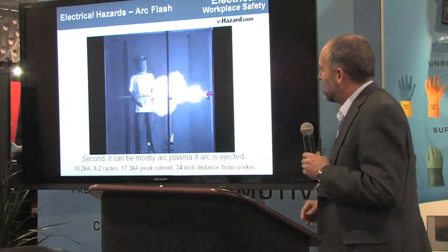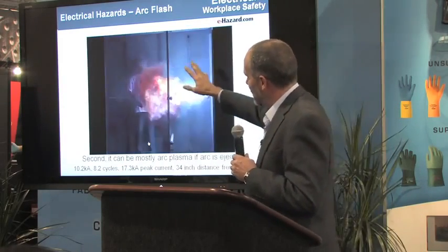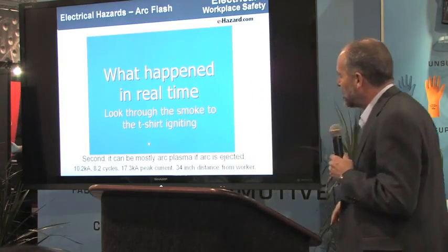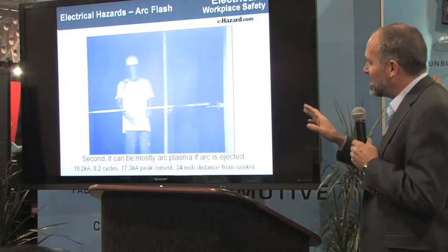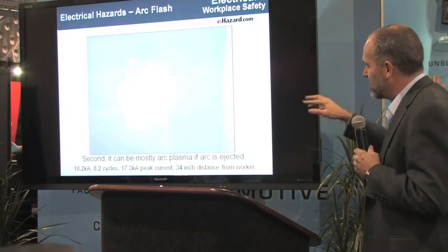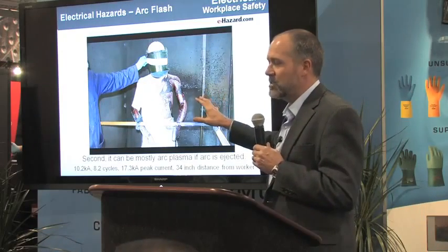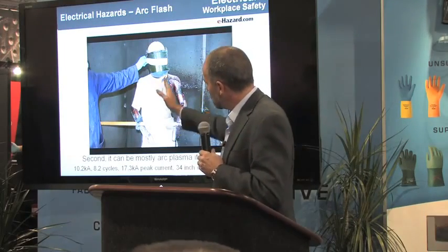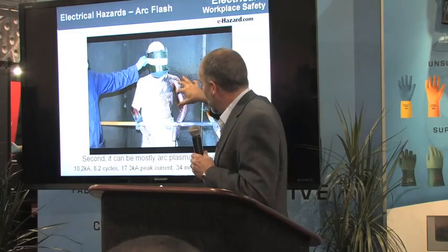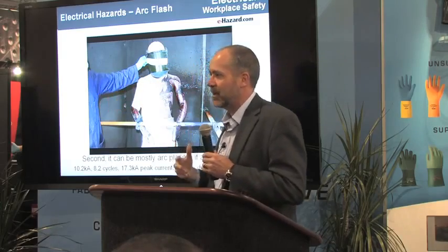Plasma is rough. It looks like just a little flowing thing coming through there. This is a sixth of a second you're watching here — here's what happened in real time. I have a cotton t-shirt on the mannequin. We hit him with that arc flash that you saw bellowing out toward him, and it was about 45 seconds it took the guy to get out there.